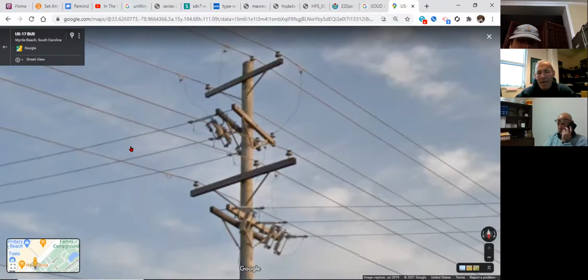This is just one of the taps that goes into Ocean Lakes. If I've got any kind of fault in there, I want to give it either 1 count or 2 count capability of clearing itself, and then the actuator will fire and open up one of these switches. So, back to your question, pretty much I'm going to hear a good many outages in this area down here in Ocean Lakes. I know right where to drive to, and I'll see an open switch.